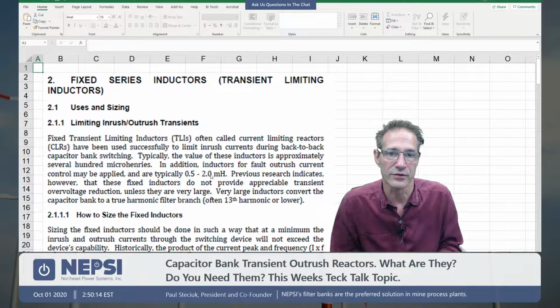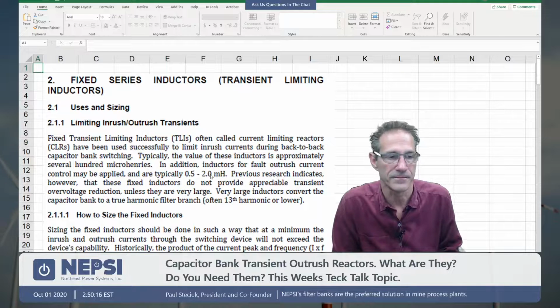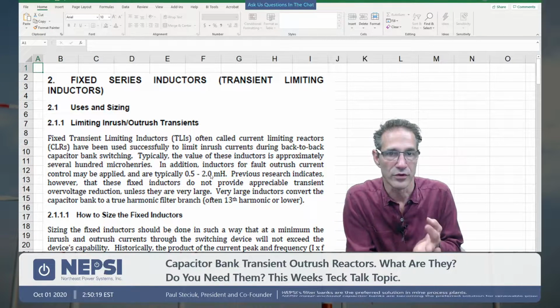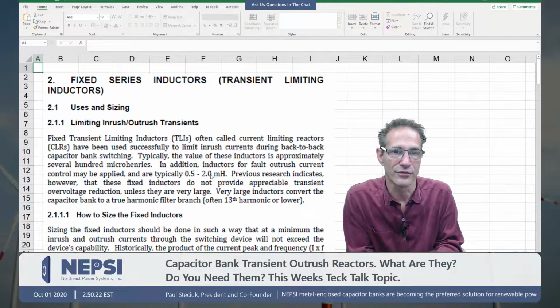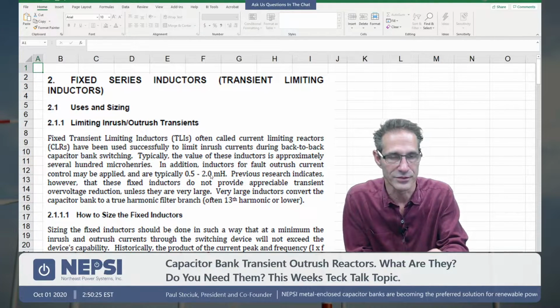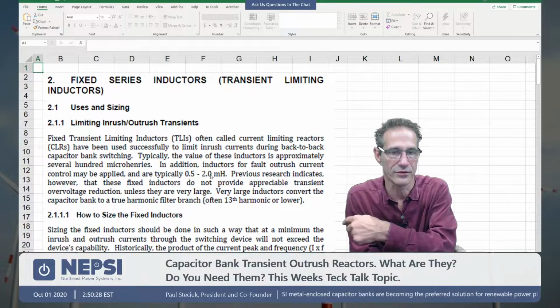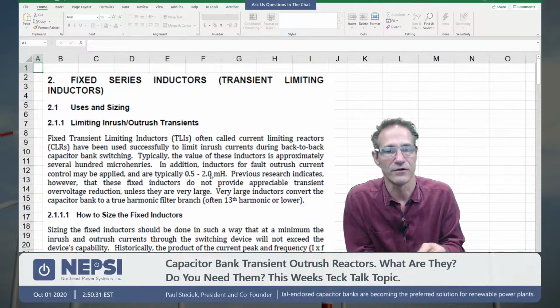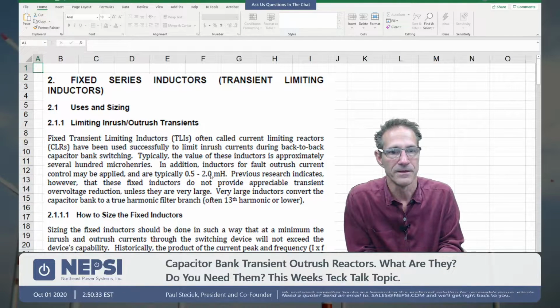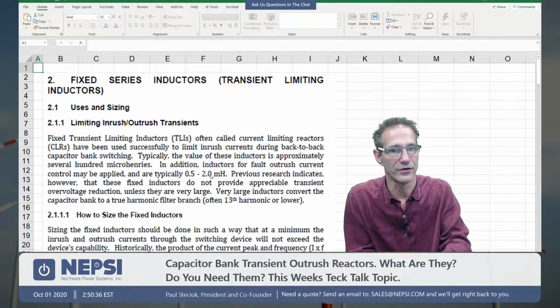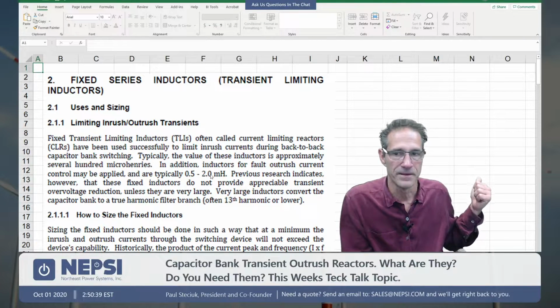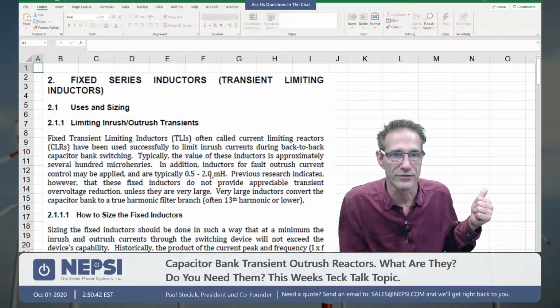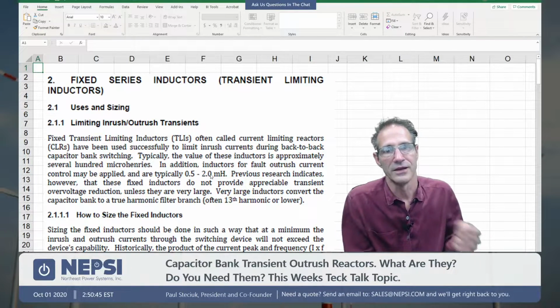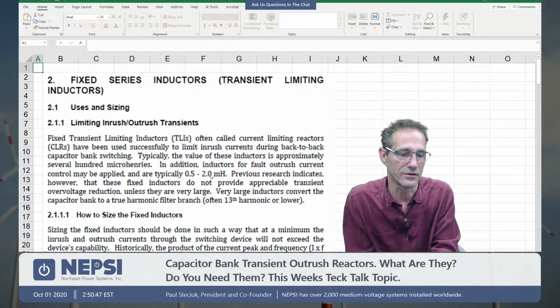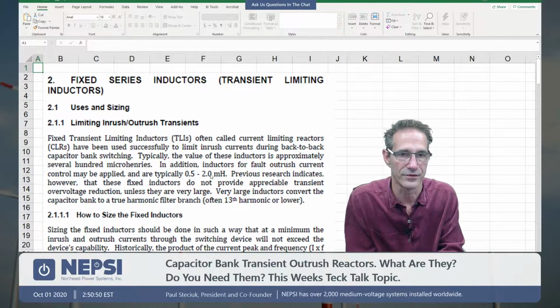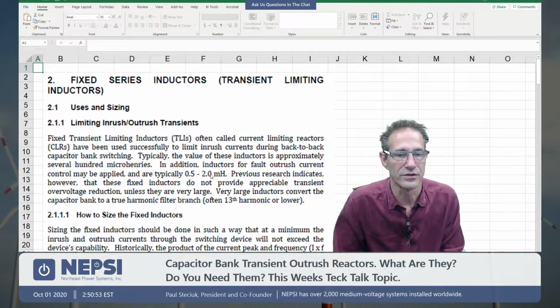Remember to always evaluate the type of fault that you have, and where the fault might occur. The fault does not always occur within a switchgear. Remember, a fault inside a switchgear is a switchgear failure. Trying to save the breaker with outrush reactors in a cap bank would not make sense. So put your first fault point someplace outside the switchgear. You know, is it within the substation itself? If you're coming in with cables, it belongs further out. And then think about what your probability of a three-phase or a phase-to-phase fault is in a capacitor bank connection. Can the capacitor bank contribute fault current to the system or not, or through that breaker? So these are things to evaluate.